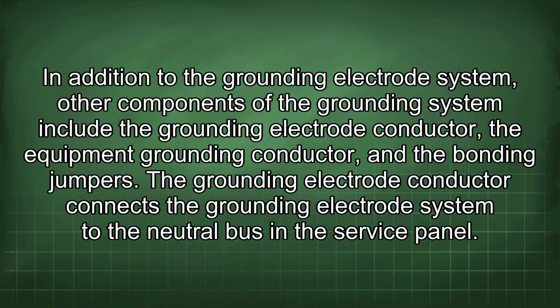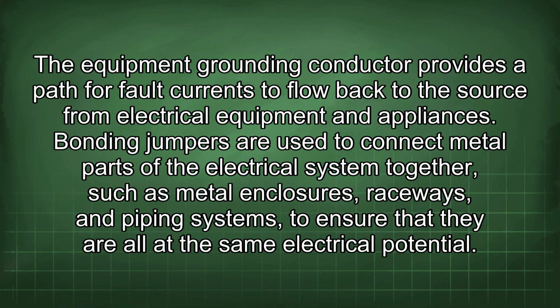In addition to the grounding electrode system, other components of the grounding system include the grounding electrode conductor, the equipment grounding conductor, and the bonding jumpers. The grounding electrode conductor connects the grounding electrode system to the neutral bus in the service panel. The equipment grounding conductor provides a path for fault currents to flow back to the source from electrical equipment and appliances. Bonding jumpers are used to connect metal parts of the electrical system together, such as metal enclosures, raceways, and piping systems, to ensure that they are all at the same electrical potential.